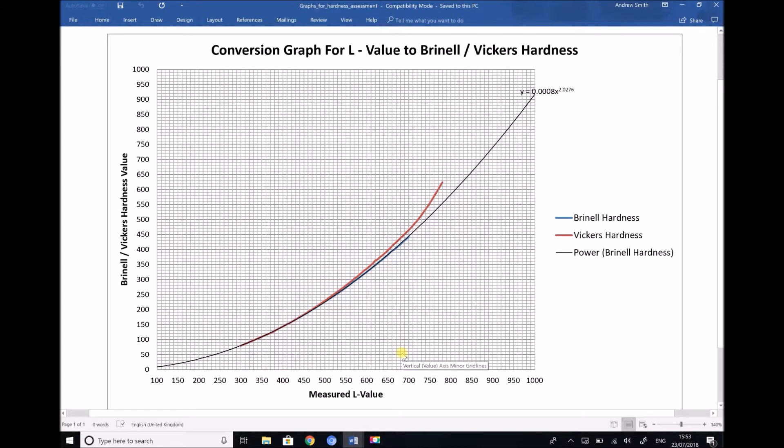Now because some of our average L values are going to be greater than 700 we've needed to extrapolate that curve in order to allow us to determine the Brinell hardnesses from those L values.